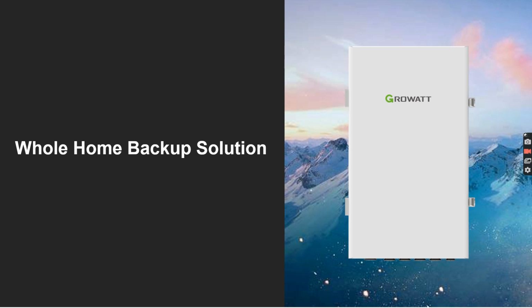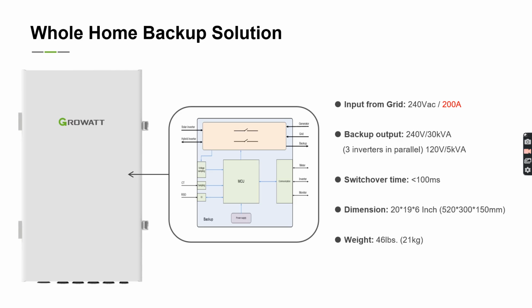In this section, we will discuss in more detail Growatt's whole home backup solutions that allow customers consistent power output to their homes in blackout situations. Growatt's whole home backup solution, also known as the ATS, will require a 240 volt AC input from the grid and is able to provide 240 volt or 120 volt output. The switchover time will be less than 100 milliseconds, allowing for seamless transfer to backup power.